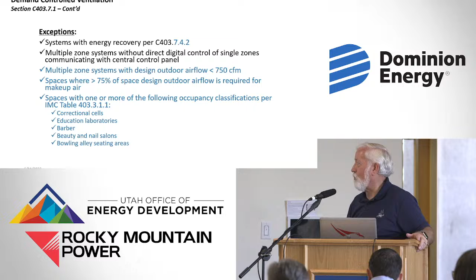Now we might have a minimum ventilation air where we're bringing just a little bit of fresh air in there just so the building doesn't get stagnant, but we modulate that. And that makes a huge difference on auditorium type assembly occupancies. And they've actually dropped it down. It was 25 people per 1,000 square feet. It's dropped down to 15 people per 1,000 feet. It's simple. It's built into most rooftop units now. A building like this that has a BMS control, it just has to be programmed in, and the sensors adjust the VAV box for this room.